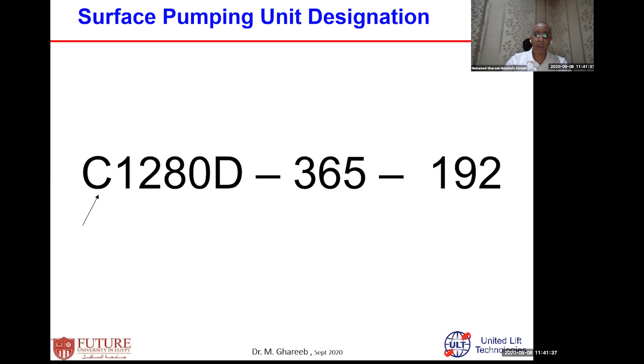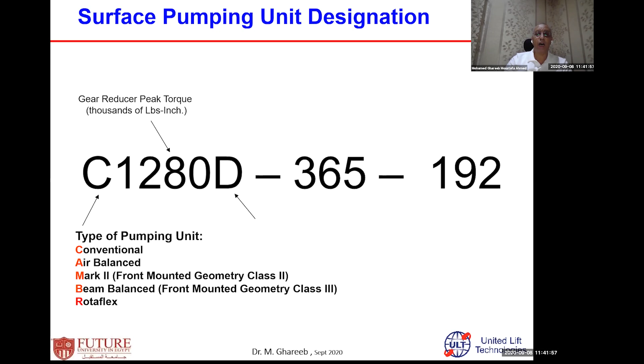The number 1280, if I multiply by 1000, means the gear reducer peak torque. It's in thousands of inch-pounds, or pound-inch. Then the second letter, D, is double reduction gear reducer. Double reduction means the gear reducer will reduce the speed over 2 steps.